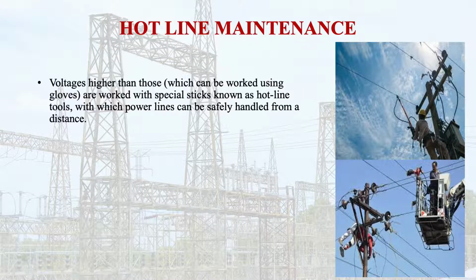When working with energized power lines, a lineman must use protection to eliminate any contact with the energized line. Some distribution level voltages can be worked using rubber gloves. The limit of how high the voltage can be for working with rubber gloves varies from company to company according to the different safety standards and local laws. Voltages higher than those which can be worked using gloves are worked with special sticks known as hotline tools, with which power lines can be safely handled from a distance. Our aim is to handle the power line safely from a distance.